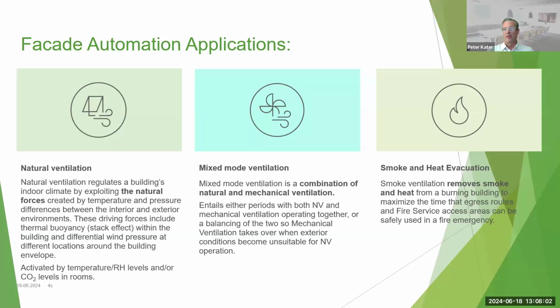The second category is mixed mode ventilation. Now, this is a combination of natural ventilation and mechanical ventilation. And this can either be where there are different periods with either one or the other operating, or periods where both natural ventilation and mechanical ventilation systems operate together to optimize the indoor air quality and achieve energy savings. The third category is smoke and heat evacuation, and this is where smoke and heat from a fire are extracted from the higher levels of a building using the operable windows. And this maximizes the time that egress routes and fire service access areas can be safely used during a fire.